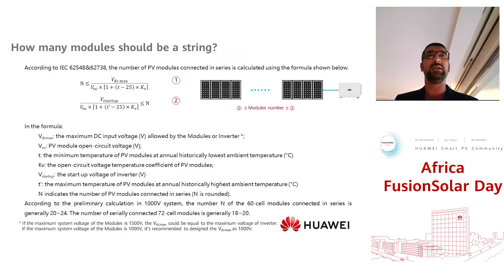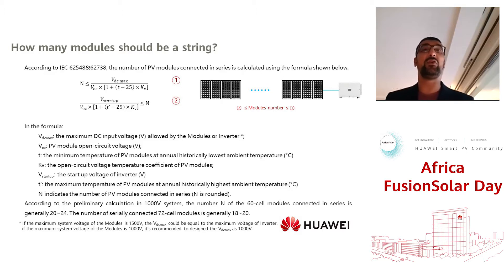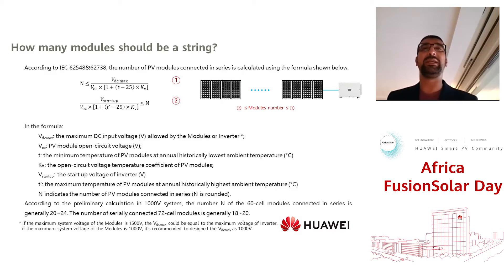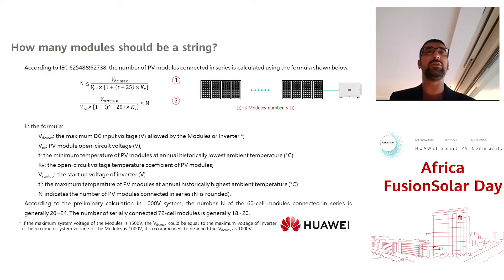In the first subject we'll be talking about how many modules per string is a suitable calculation. We'll follow the two IEC standards: IEC 62548 and IEC 62738. Both of these standards are applicable to the application of solar and configuring the minimum and specifically the maximum number of modules that can be connected in a string. Each PV module has a voltage value, and the more modules in series you connect, the higher that string voltage will become.